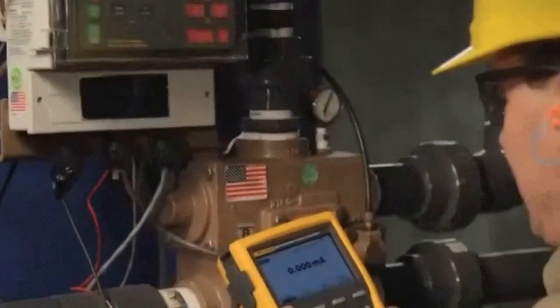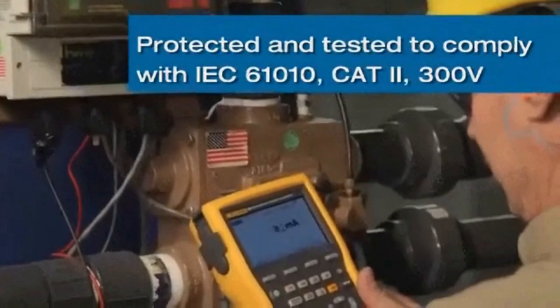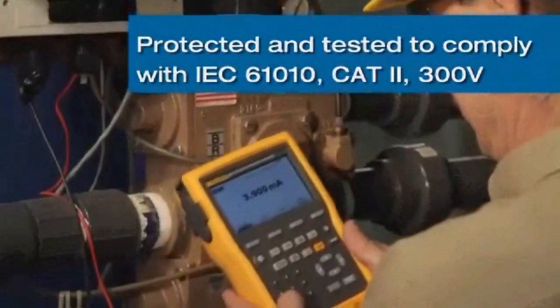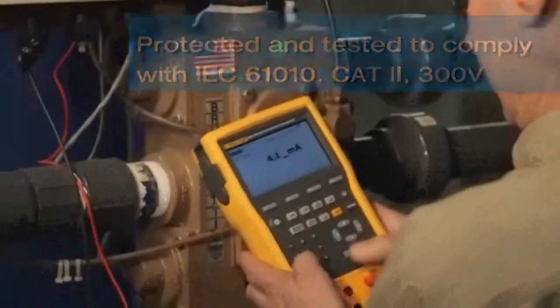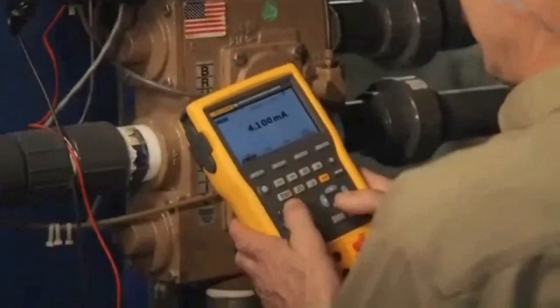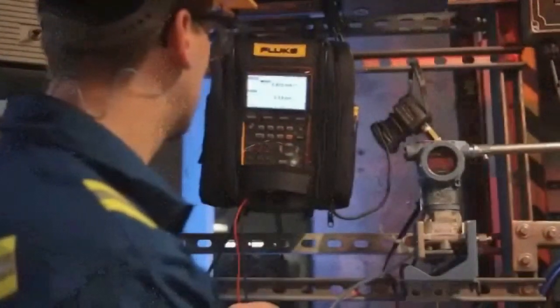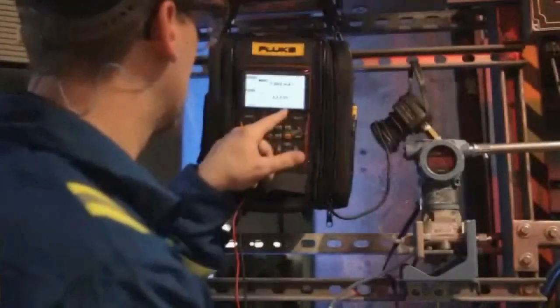The 750 series calibrators are uniquely protected and tested to comply with IEC 61010 CAT 2, 300 volt. What this means to you is that if you misapply either 120 or 240 volts AC, these calibrators are designed and warranted to survive and keep on working.